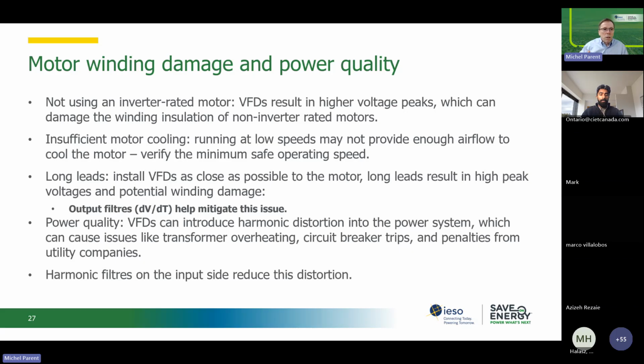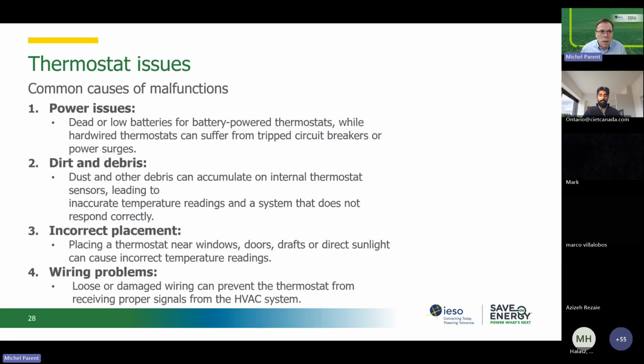That will help to reduce the issues with long leads. So if you cannot install the drive close to your motor, and this has nothing to do with the previous problem, which is the grounding. This is a different issue, it's about the high peaks. You've got a VFD that's far. It's going to send high voltage peaks to your motor, even if it's inverter duty. So you will need to have a filter, an output filter, which is called a dV/dt filter.